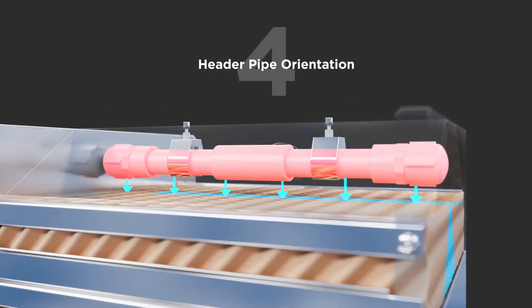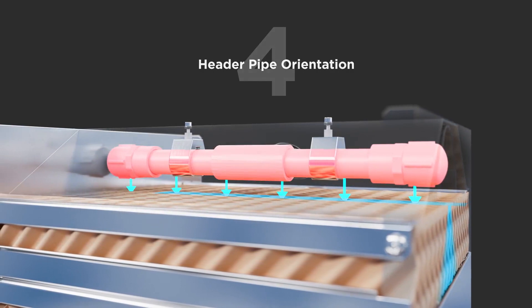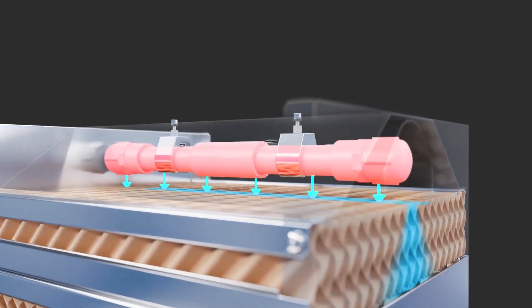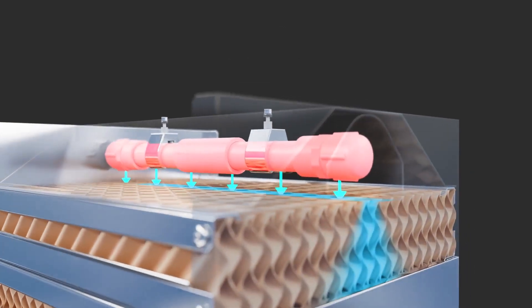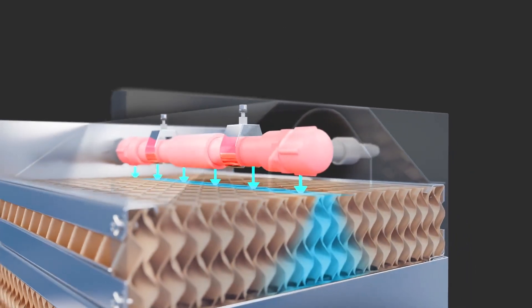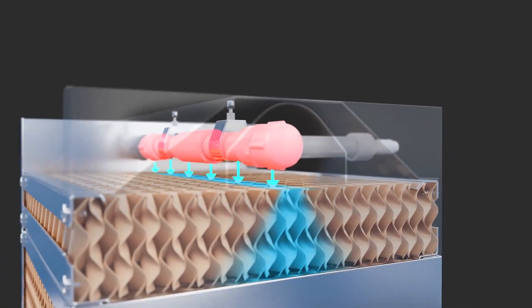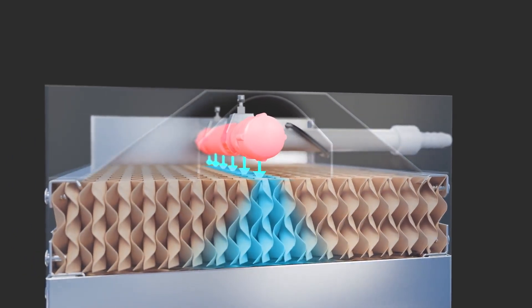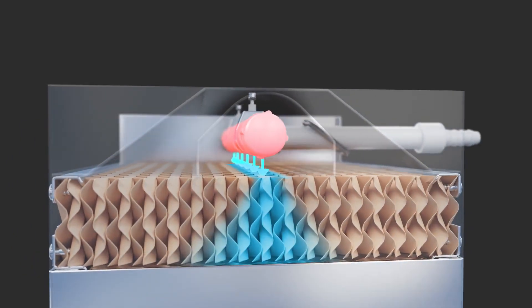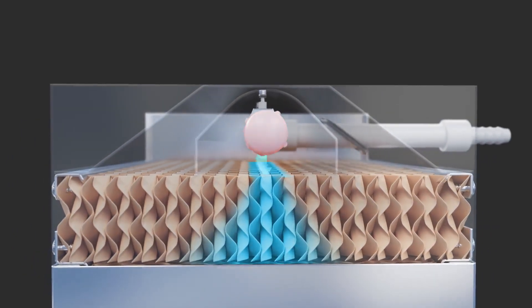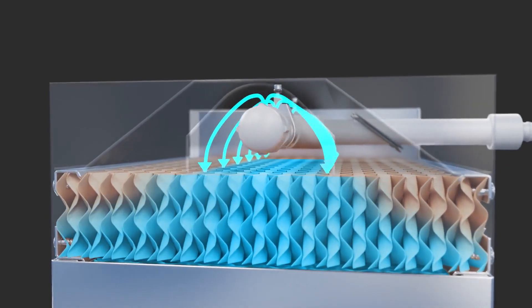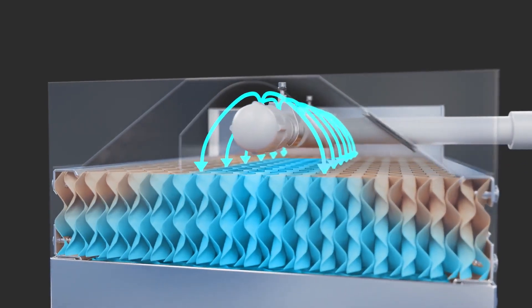Improper header pipe orientation. When the header pipe points directly down at the media, it can lead to water particle overload and reduced efficiency. Align the holes upward at a 90-degree angle to create a parabolic water stream and even distribution.